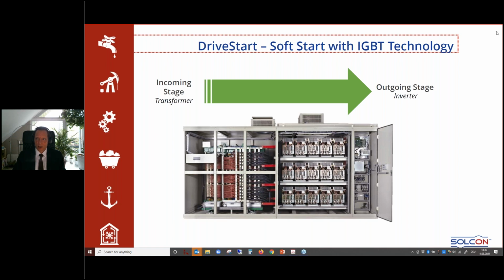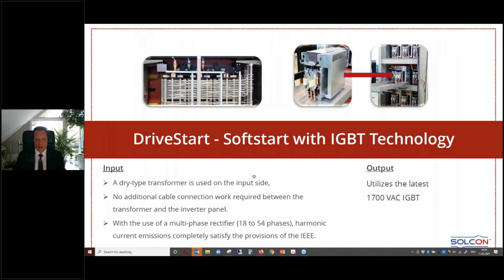So here you see how a typical drive start looks, from the components. You have an incoming transformer, multi-winding, you have low voltage IGBT cells, and you have the outgoing cell, which is going then to the motor. It's a dry type transformer on the incoming side. Between the transformer and the IGBTs, there is no additional cabling necessary. We are utilizing here the latest 1.7 kV IGBTs, which is a very high voltage compared to the actual output voltage of the IGBT. It's low voltage.